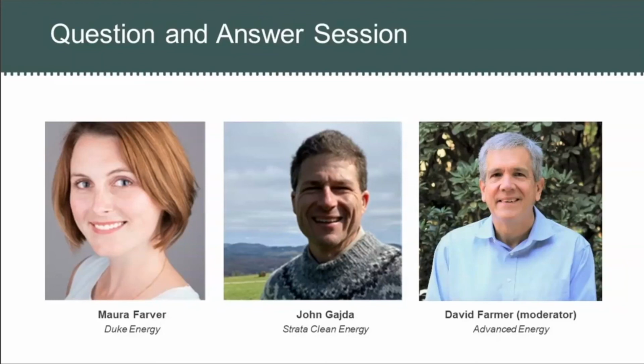Yeah, thanks, John. I'd agree, based on our experience over the years working together, that's about as good an answer as you can come up with. From the Hawaii perspective, particularly with rooftop solar, it can be a problem that sneaks up because you're not studying each individual interconnection. When you're looking at utility-scale solar, you're doing a study and looking at the impact. But in Hawaii, when it just took off, they had feeders on their system with up to five or six times the power flow than the daytime minimum load, coming from generation. That was beginning to cause a problem, and Hawaii's got the added problem of being an islanded grid, there's not a larger grid they can absorb that extra into.